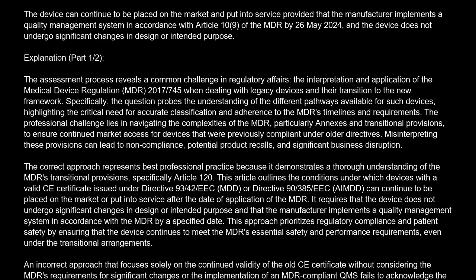The correct answer is C. The device can continue to be placed on the market and put into service provided that the manufacturer implements a quality management system in accordance with Article 10(9) of the MDR by 26 May 2024, and the device does not undergo significant changes in design or intended purpose.